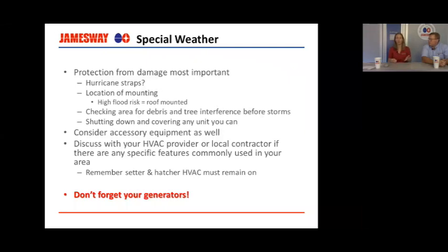Don't ground mount your HVAC if you're in a high flood area. Before a major storm comes through, have your maintenance guy, have somebody go out and check, is there any debris on the roof that they've left up there when they were fixing something that could become a projectile and damage your equipment? Are there any trees or poles or something that could fall in high winds? And shut down and cover any unit that you can for additional protection. Don't forget about your accessory equipment, your fans, everything should be protected if you can.